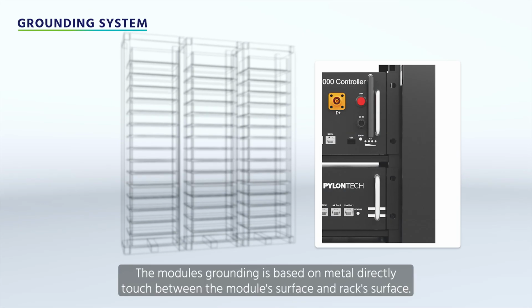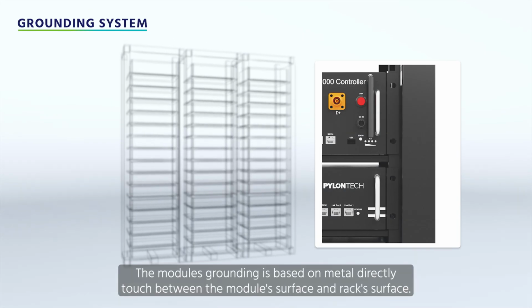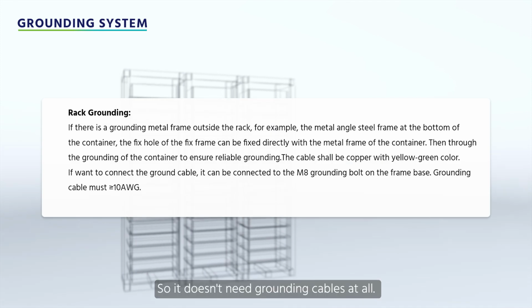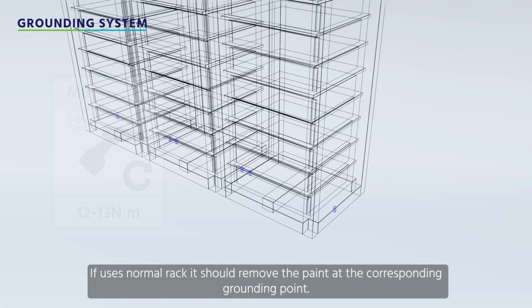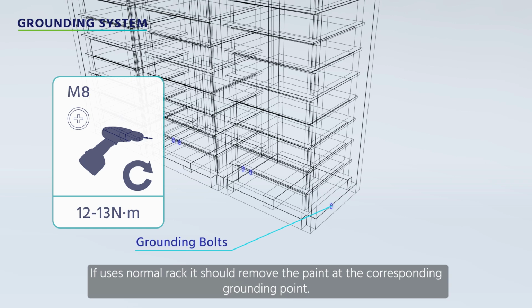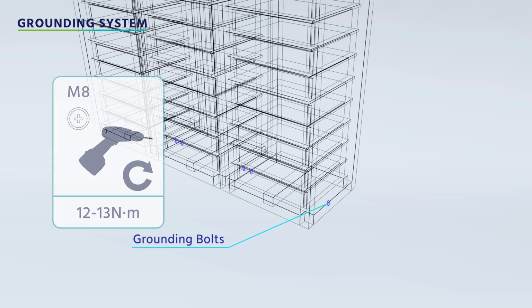The module's grounding is based on metal directly touching between the module surface and rack surface, so it doesn't need grounding cables at all. If using a normal rack, you should remove the paint at the corresponding grounding point.